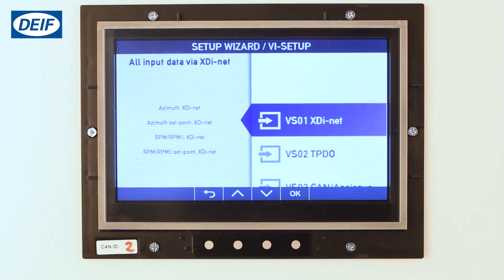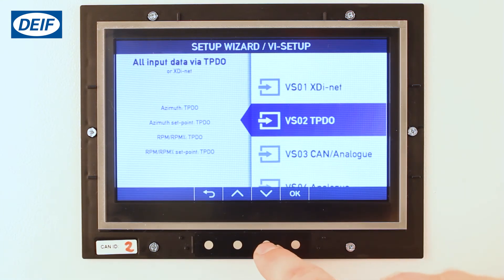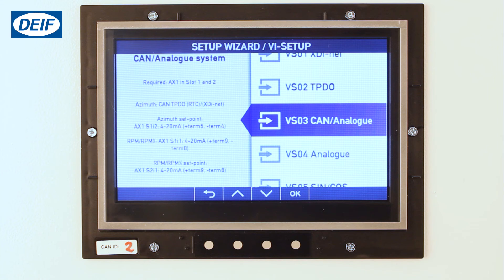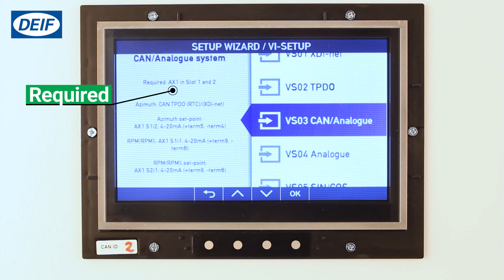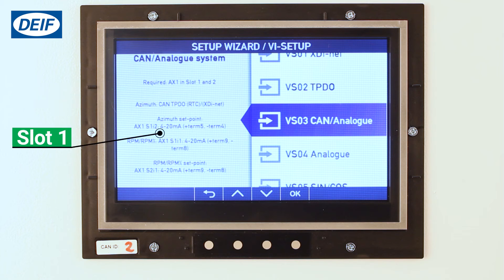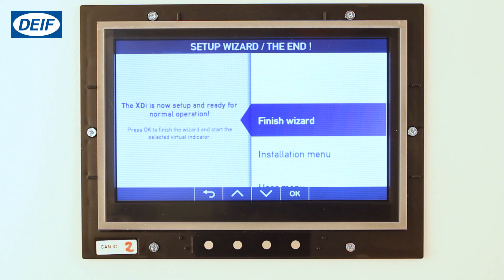The virtual indicator setup profile is now shown. This is where you select your input sources. The setup profile also contains preset parameters for scaling, labels, units, and more. Use up and down to select between the different setups. In our case we will use VS3 CAN analog. This requires AX1 modules in both slots one and two. In slot one, this is for the azimuth setpoint and the RPM value from the transducer. In slot two, this is for the RPM setpoint. Select OK to confirm the setting.